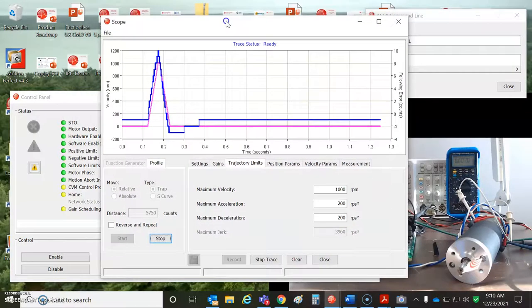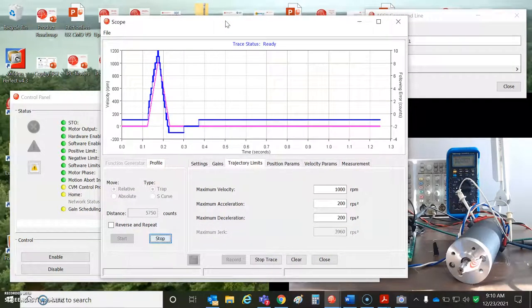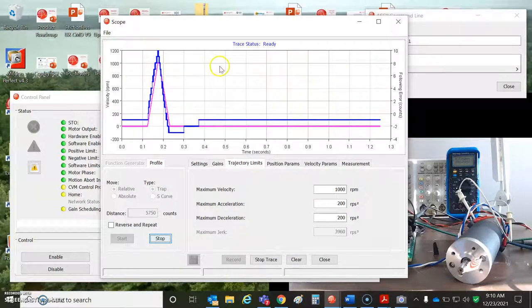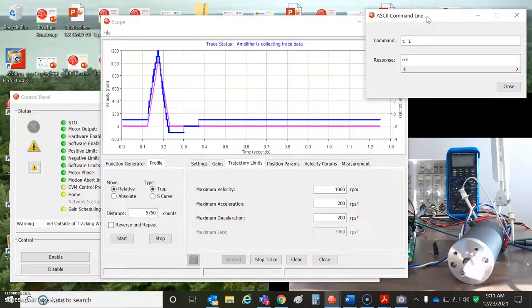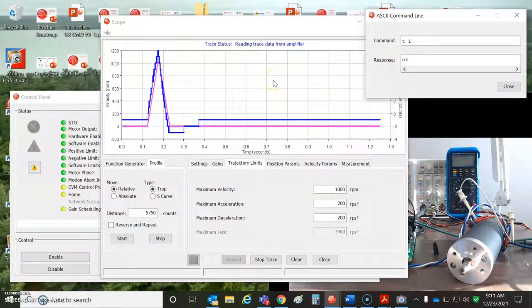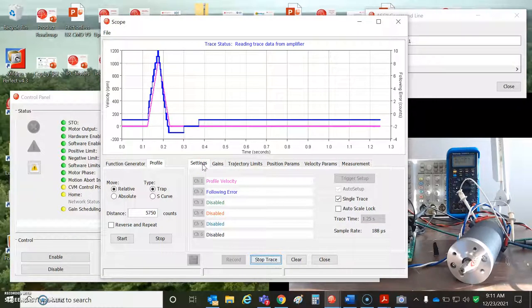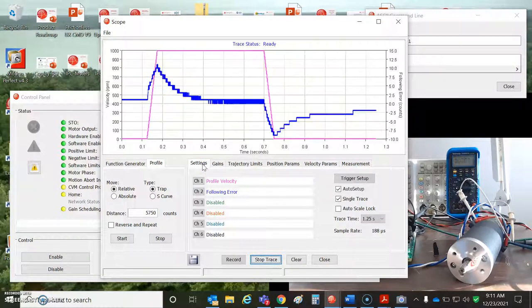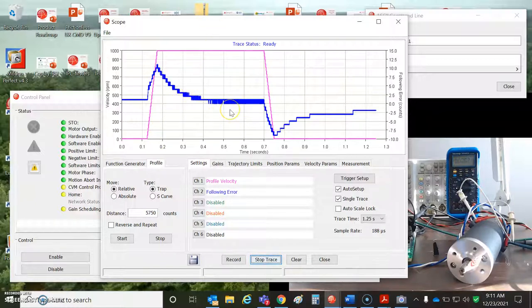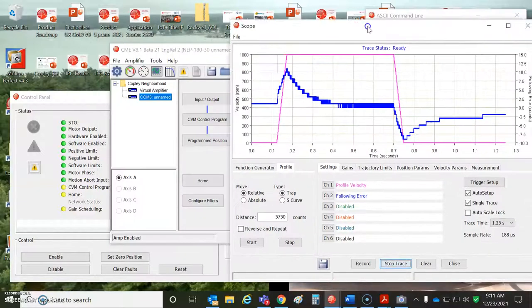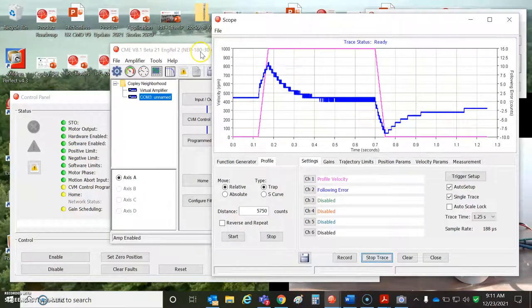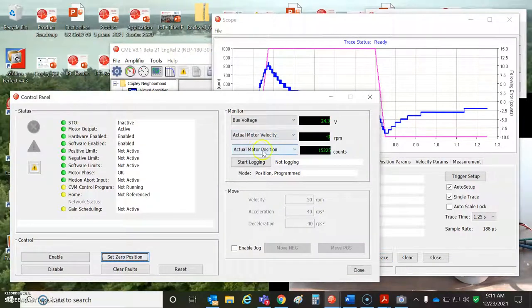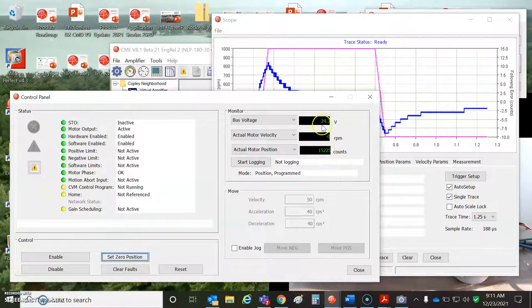See, pseudo position, you gotta have a position observer somewhere to make sure you're not smashing into the hard stop. Let's see if I can get a trace of that. You can also monitor the voltage, power supply, the voltage limit warnings, the current. I'm just looking at the profile velocity and the pseudo position following error while we move. It looks tuned rather well, so that should be good. And here's the position, pseudo position.